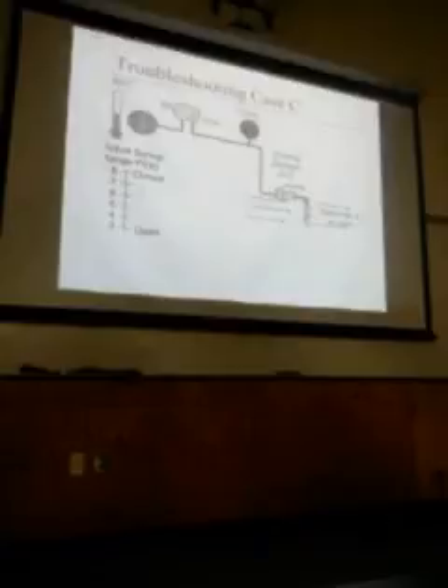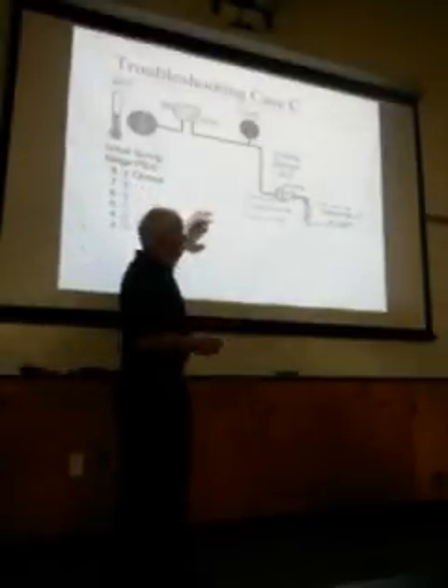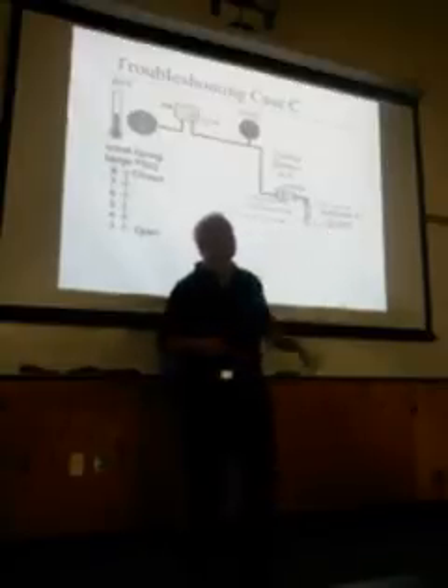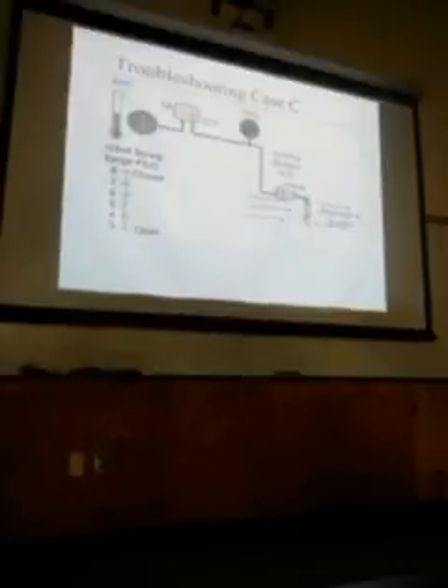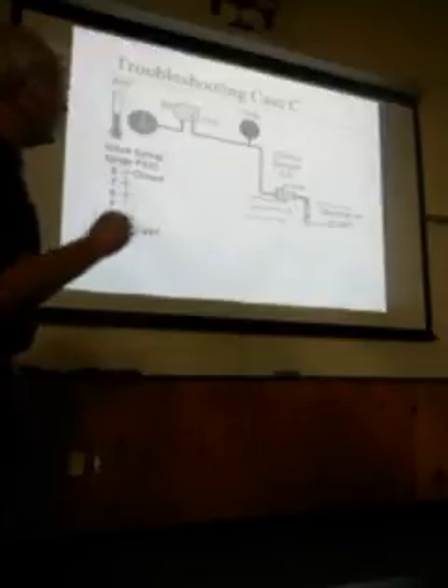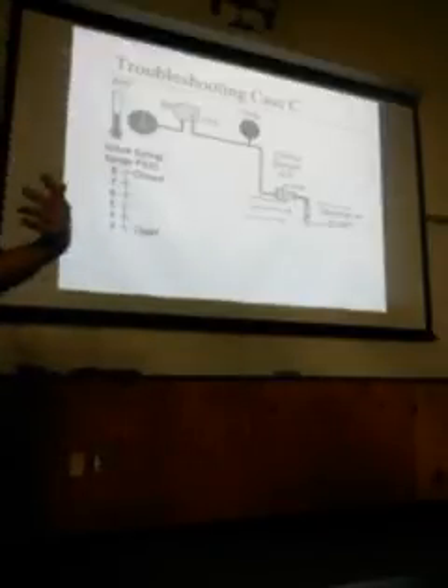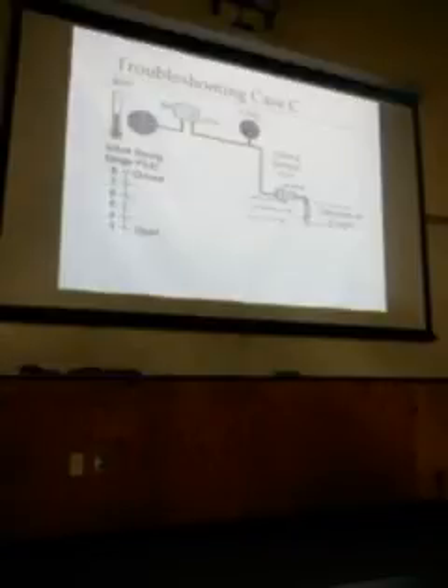So in a normal system like this, it should be like 55 degrees going in that space, wide open. You could have a hot deck issue that's not working right over back in the system. The point here is that, yes, something's definitely wrong, but in this case, it's not here yet. And assuming your gauge is good, it's not there. So, we don't want any pressure on this actuator. So either this actuator froze in the closed position, or we have 0 airflow, or we have airflow that's inappropriate for the condition. Like we have 80 degree air going into this space instead of 55. Could be all the way back to the economizer. A lot of times you just got to work your way back through the system to see what's going on.